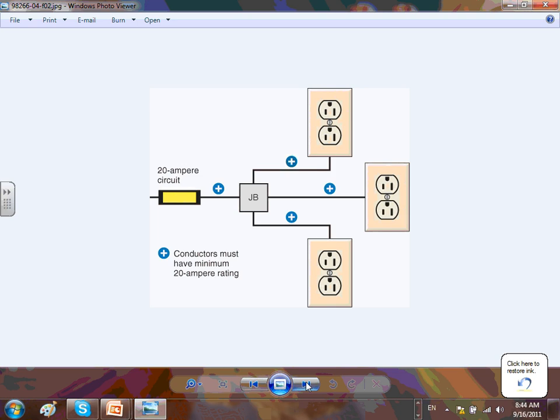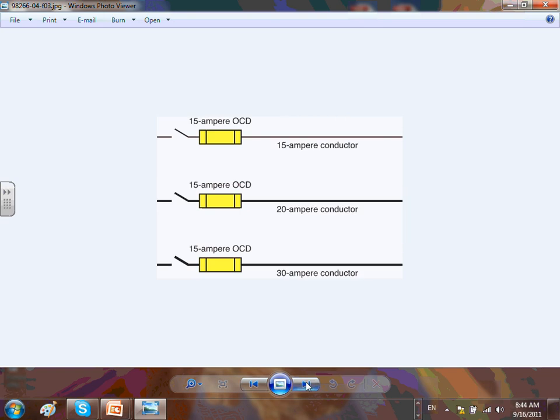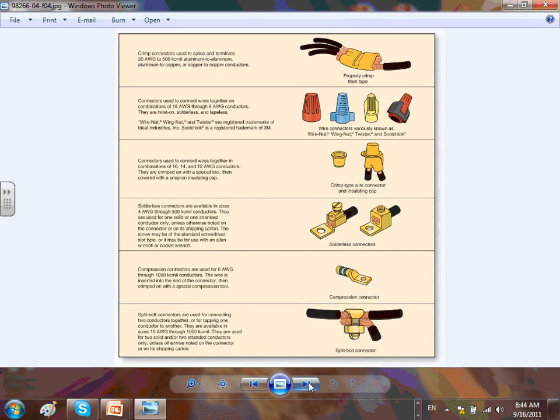We talked about the 20 amp circuit going from a J-box — the conductor must have the minimum ampacity for the circuit. The rating of the circuit follows the rating of the overcurrent device, not the conductor size. If you were electricians, you would talk about taps and tap rules.